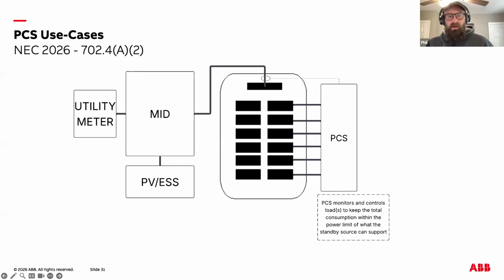Article 702 covers the rules for optional standby systems, which is where most battery storage exists in the NEC now. And Section 702.4 focuses specifically on how those systems must be sized and rated. The core idea is that the standby source must be able to support whatever loads it is expected to carry, but the code treats manual and automatic systems differently.